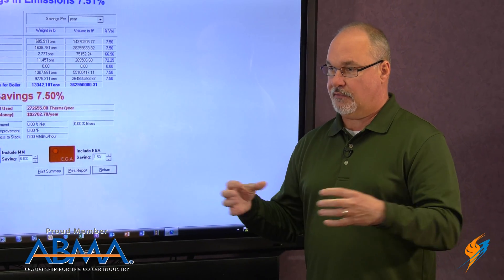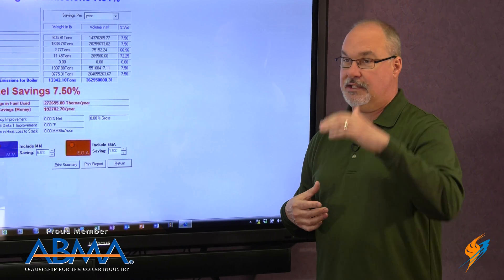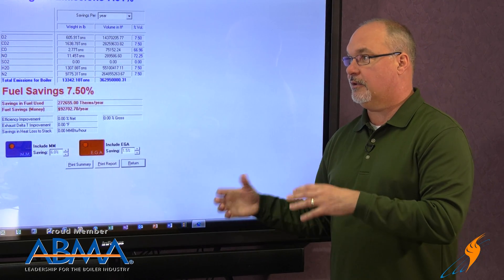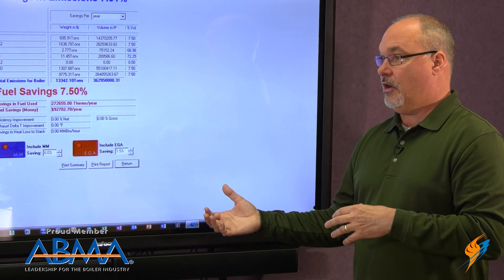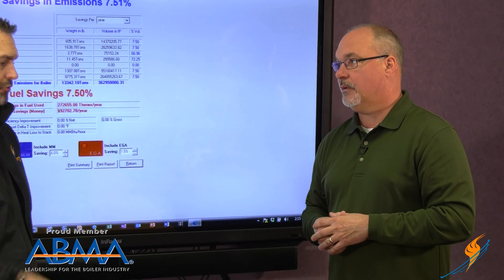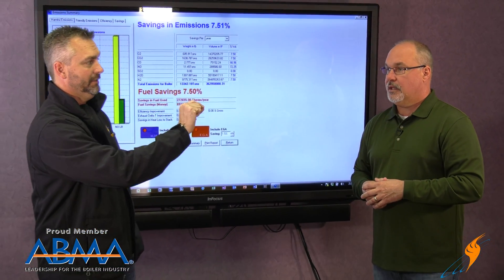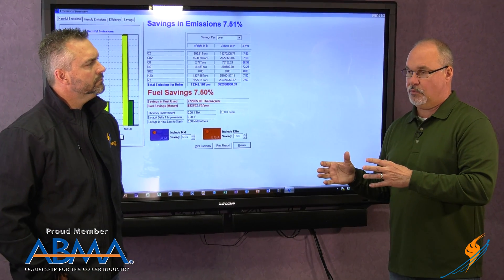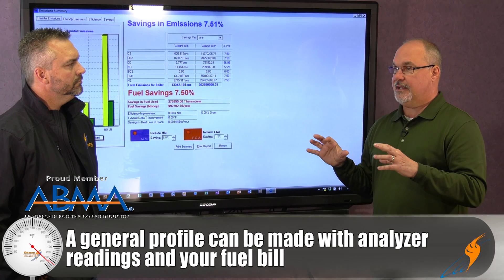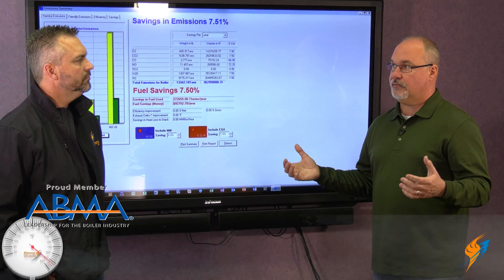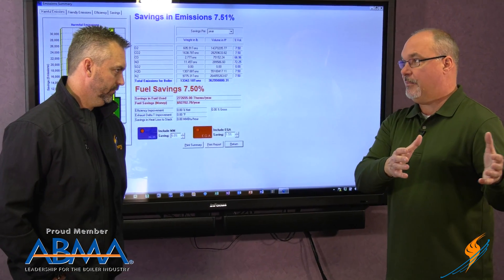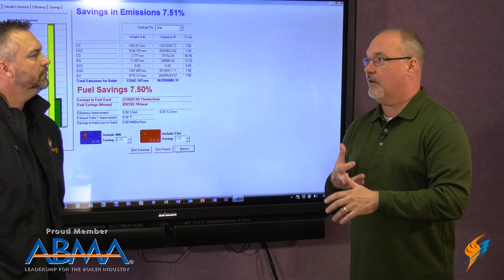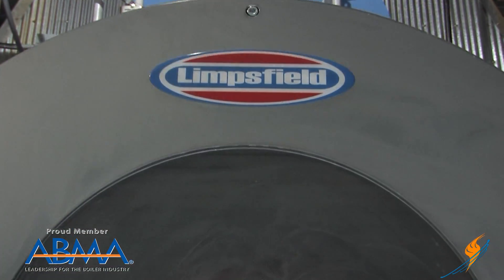More detailed information to make sure everything's matching up would be analyzer readings to see the exact combustion performance at different levels, and what the fuel costs are. We can make estimates by going to the internet and looking at fuel prices, knowing how often you're operating, and getting your gas bill for comparisons. The actual load — how the boiler is running through the day, what type of turndown — is helpful too. Usually our comparison with analyzer readings and the fuel bill can give us a general profile, plus having a conversation with the guys involved with the equipment. It usually starts with the basics: give us the size of the boilers and how often you operate, we'll run a preliminary estimate and work our way down to the final numbers.